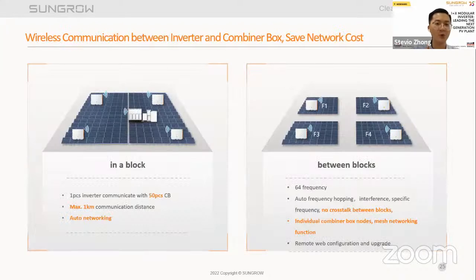Compared with the traditional hardwired RS485 communication, the wireless communication between inverter and combiner box helps to save network cost. The label cost, the wiring cost, and the cable cost, the operation and maintenance cost, and troubleshooting cost could be saved as well. In a block, the maximum number of combiner box which could communicate with inverter is 50. The communication distance between the inverter and combiner box is 1 kilometer at most. The networking could be built automatically.